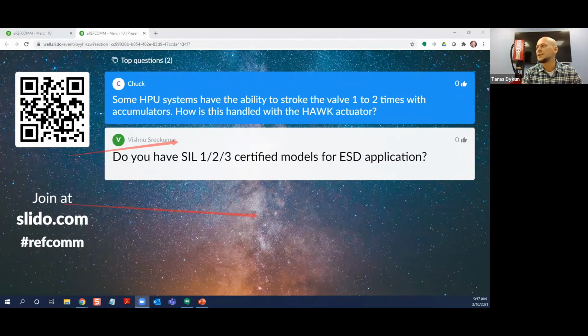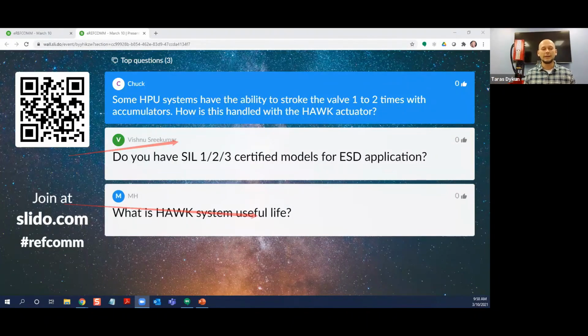But with this, I would like to ask you a question. When do you really operate this unit in a manual mode, or whenever you need to stroke it 1 or 2 times? It's really only the ESD portion which requires you to close the valve and make sure the valve is closed. And if you have an additional stroke or any ESD event, you need to close it. But whenever there is a power loss or anything else, that valve is locked in place anyway, right? I've been working for MEA for over 6.5 years, and I used to work a lot in field service, and I have not seen a request where there is a power loss and you're actually using this hydraulic energy to position the valve. It's only if you really lost the power to the motor or something. So I just don't know this scenario. Maybe you guys do. If you do, please let me know. I would like to know that.